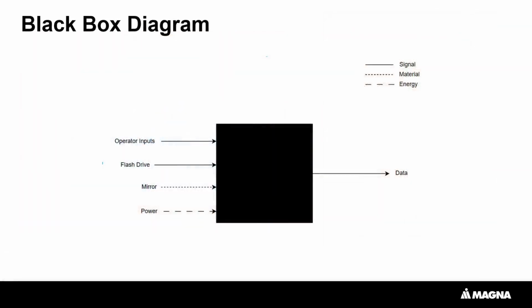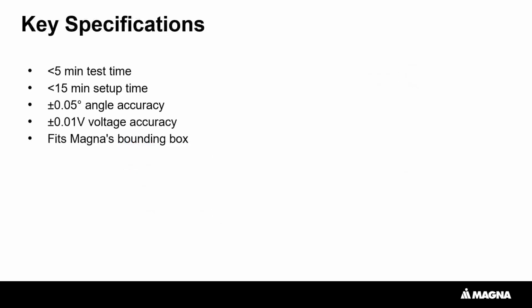Our objective was to create an automated test platform that reduces setup time and error while accurately capturing mirror position and voltage data for quality assurance. Our solution needed to meet strict performance specs, including under 5-minute test cycles, under 15-minute test setup, precise angle and voltage measurements, and it must be portable and compact.